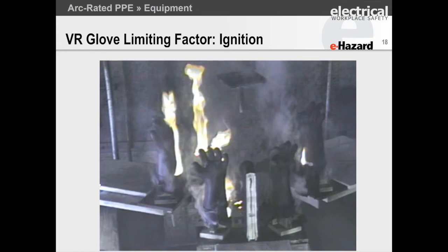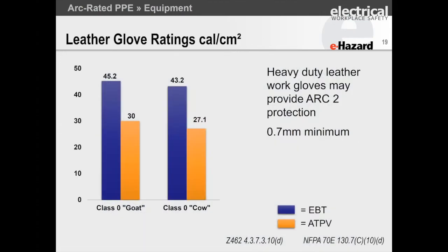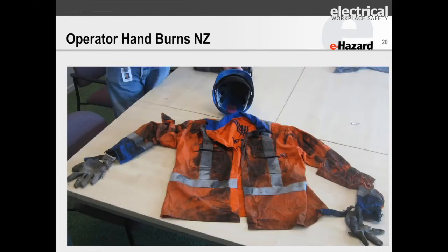The arc-rated protectors are soon to be on the market. Leather gloves provide a very good protection value, as you can see here, and they are fantastic to protect the rubber insulating glove from igniting. Now, in New Zealand, we had an accident where a guy got his hands burned because he was wearing non-FR cut-resistant gloves. There are arc-rated cut-resistant gloves out there. This guy got no burns except on his hands because the gloves caught on fire on the back of his hands. You can see they didn't catch on fire where the coating was. The coating was actually somewhat flame-resistant, but the back of the hands both got burned, and fairly severely in this case.